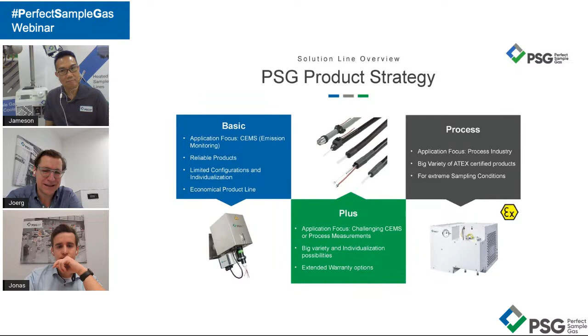Okay, Jameson, I think now it's you giving us an overview. What are the new requirements, and why would we call this the heart of the sample handling system? Yeah. So why do we call it the heart of the sampling system? When we talk about conditioning, we want to condition the sample so that it is conducive for the gas analyzer to measure. Most of the gas analyzers in this field would be infrared. Yeah, there are also UV and electrochemical ones. One of the things that we want to do is remove condensation. The whole entire sampling system for emission monitoring always narrows down to one word: condensation. If we're able to remove condensation, you are able to have a very robust sample conditioning system. So how can we remove condensate? That lies in how effectively and how you choose the gas cooler.